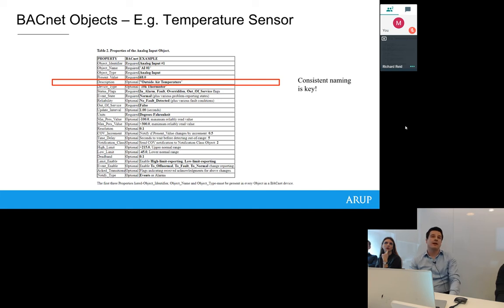BACnet is an open protocol, or perceived as an open protocol. It's not truly open because every single manufacturer has their own engineering tool. So even though I'm talking a common language, I'm still locked into that manufacturer because I need to know how to use their engineering tool, and I have to pay for it. When a temperature sensor is defined in BACnet, it gets a description, and the name could be anything you want it to be.